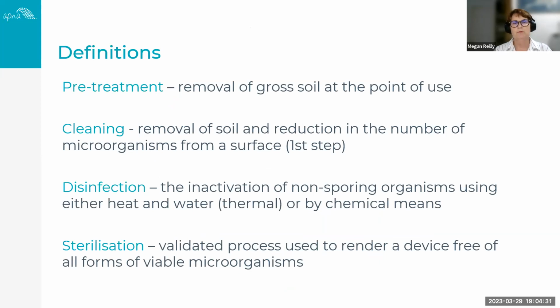So there's sometimes a bit of confusion between the terms pre-cleaning, initial cleaning or initial treatment, but I suppose the official definition is pre-treatment, and this is when we're removing any gross soil at the point of use wherever possible. Cleaning is the removal of soil and the reduction in the bioburden or the number of microorganisms on the surface, and that is always the first step in reprocessing and the most important step, because if we do not clean our RMDs effectively, then the next step, whether that's disinfection or sterilisation, is not going to be effective.